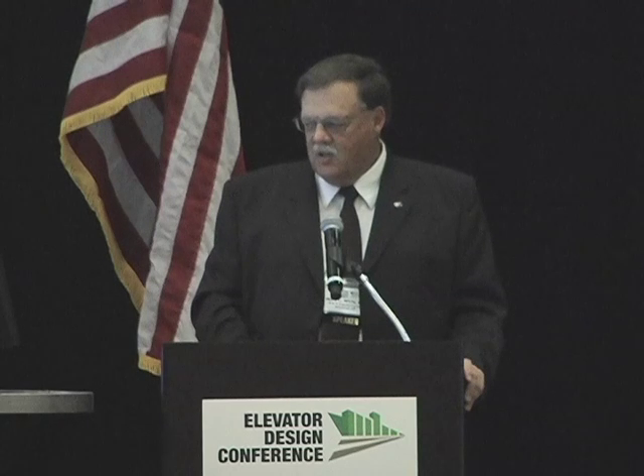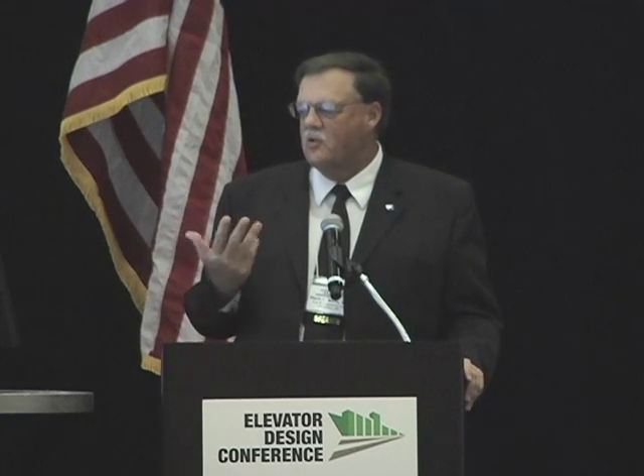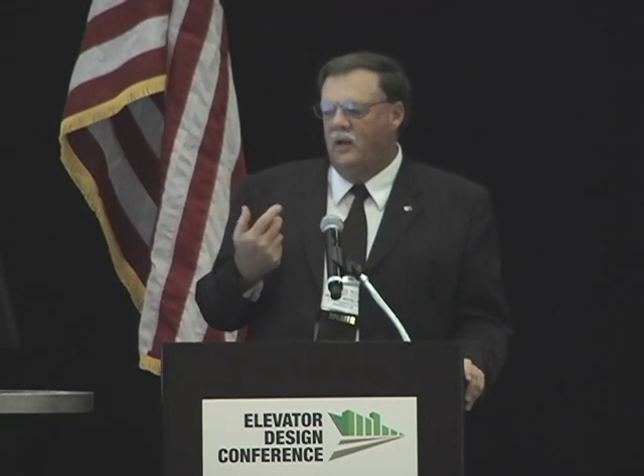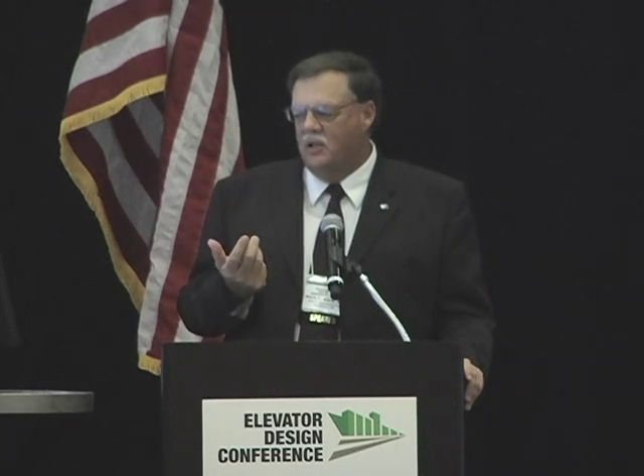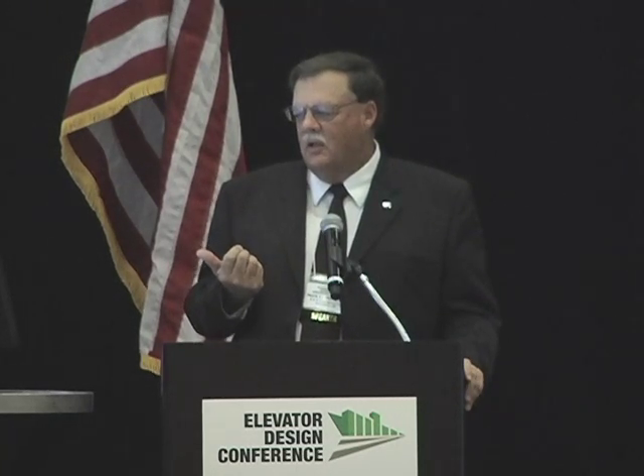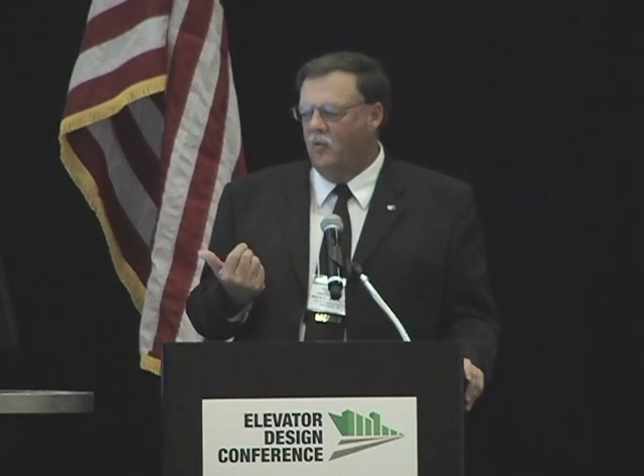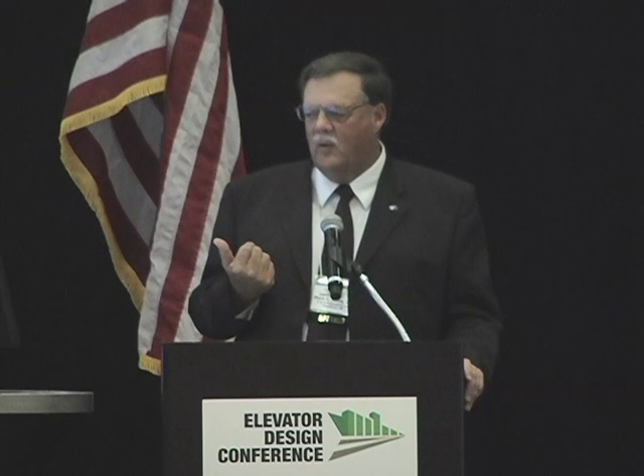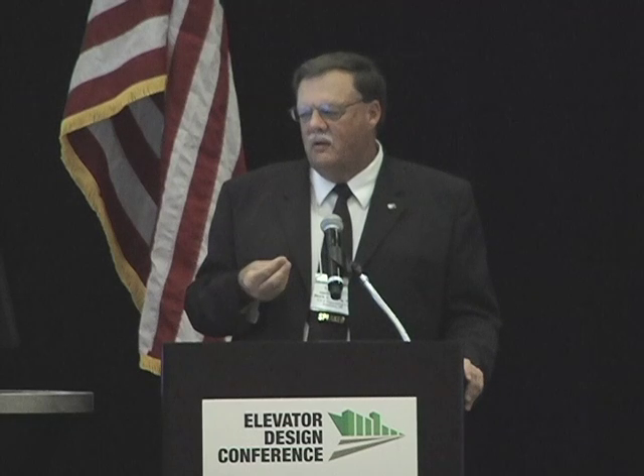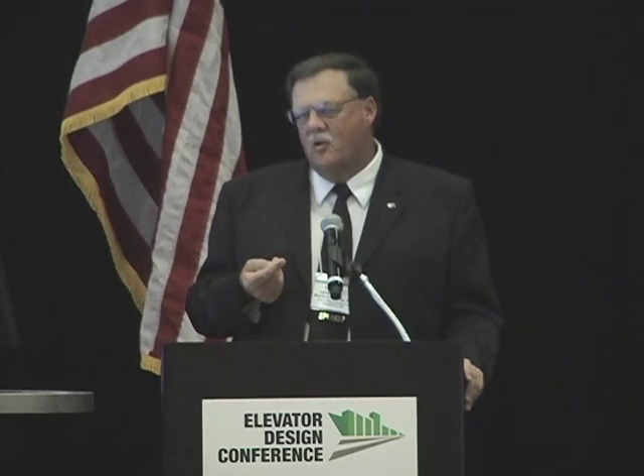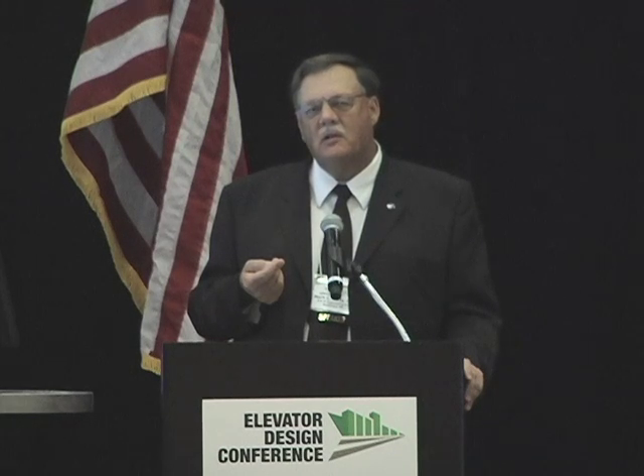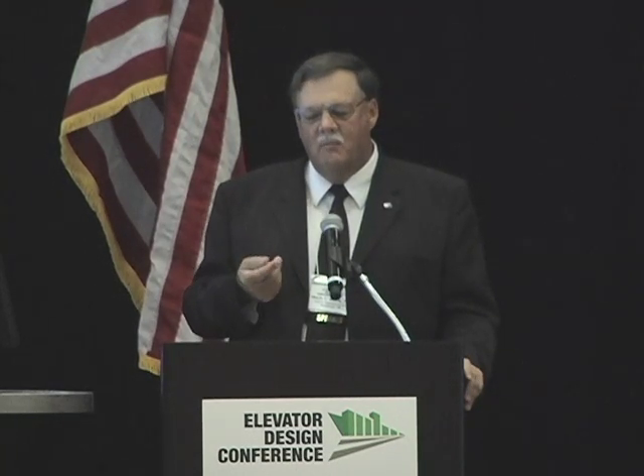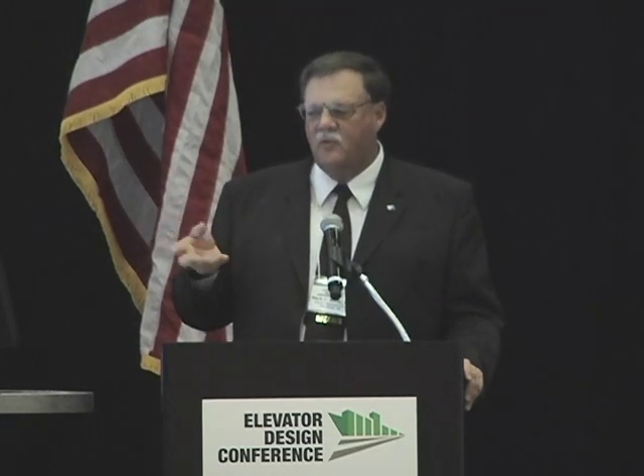So I'll get a little bit into hazardous location issues, as you've heard before with dust and so forth. In the electrical world, we have a relationship to NFPA 61, and obviously in NFPA 70, the National Electrical Code, Articles 500, 502, 504 cover dust hazard location wiring requirements. There's another standard, NFPA 499, that I use quite frequently, and even though the title says for petrochemical facilities, the principles are the same, but it is a standard for methodologies of classification for hazardous dust. 497 is for gases, 499 is for dust.